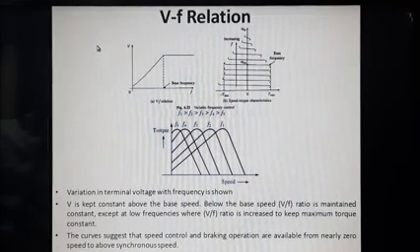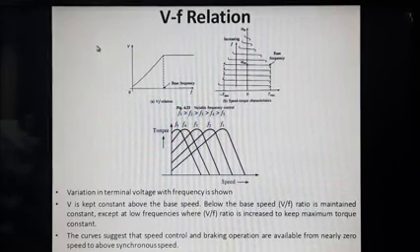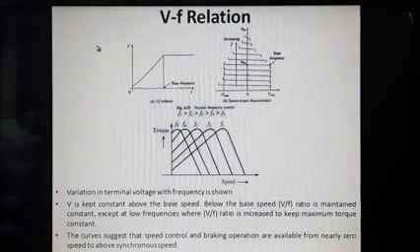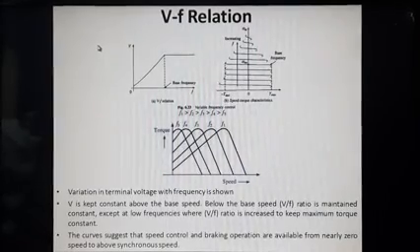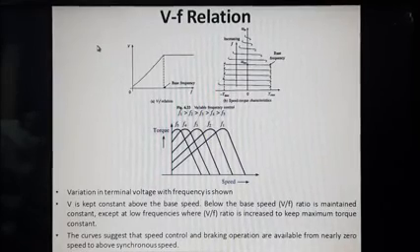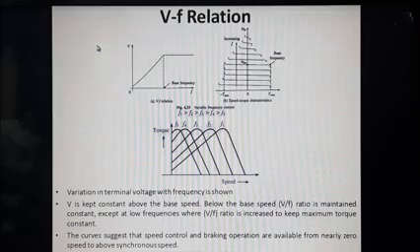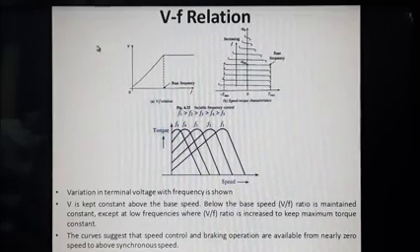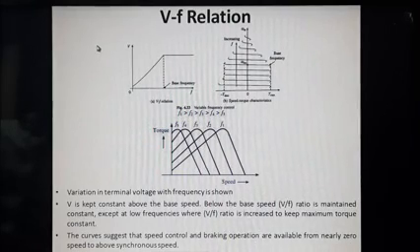And if you are trying to increase the frequency, then also there is a problem, that is the maximum torque capability, because Tmax is directly proportional to V by F square. So if you are trying to increase the frequency without bringing any change to the voltage, then the value of Tmax will get reduced.